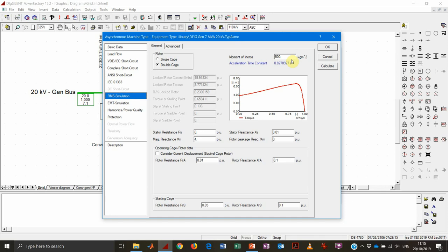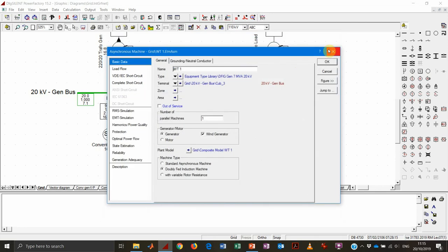The rest of the wind turbine — not the electrical generator, but actually the rotor and the blades — accounts for a little bit more than seven seconds. So all in all, the wind turbine has around eight seconds of acceleration time. But as we will see in the exercises, this moment of inertia basically contributes for nothing, unless we modify the control loop to release some of this kinetic energy for inertia response.